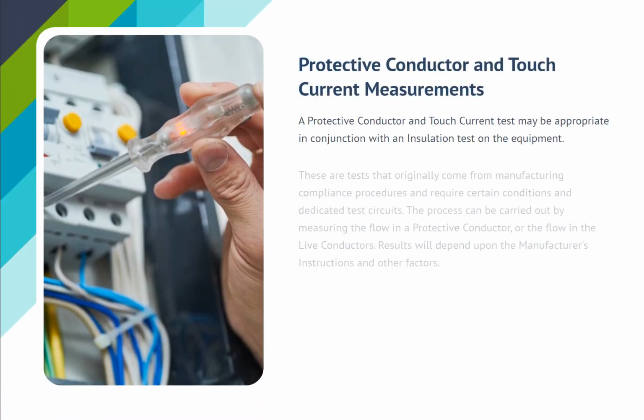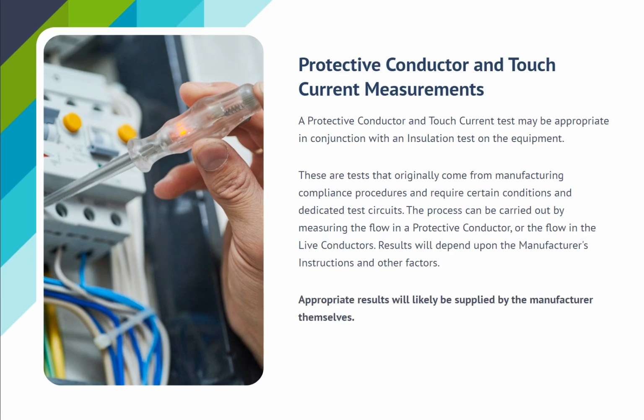Protective conductor and touch current measurements. A protective conductor and touch current test may be appropriate in conjunction with an insulation test on the equipment. These are tests that originally come from manufacturing compliance procedures and require certain conditions and dedicated test circuits. The process can be carried out by measuring the flow in a protective conductor or the flow in the live conductors. Results will depend upon the manufacturer's instructions and other factors. Appropriate results will likely be supplied by the manufacturer themselves.